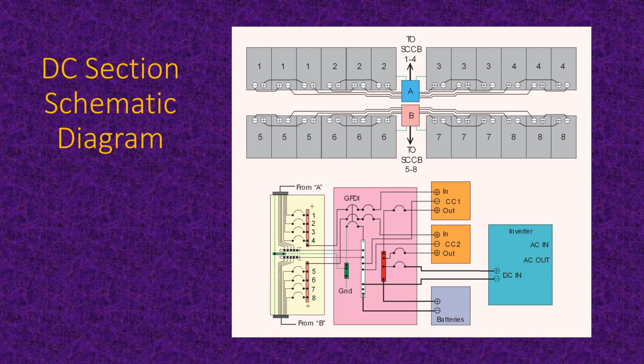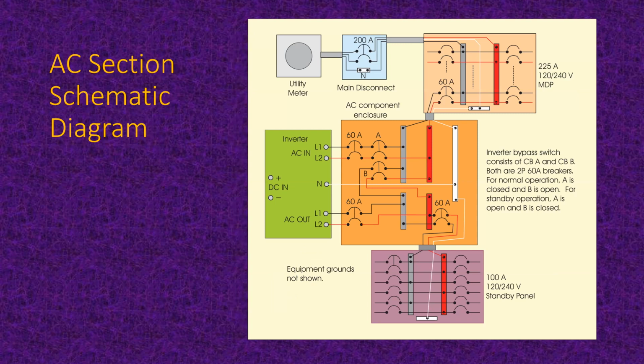Okay, there's your schematic. Here's the AC side. Utility meter, main disconnect, 60 amp breaker feeding the main distribution panel. Then we've got the inverter bypass switch here that is now 2-pole bypassing in case you want to take the inverter out of service. The standby loads down below, the AC in, the AC out. So that's the AC half of this system.